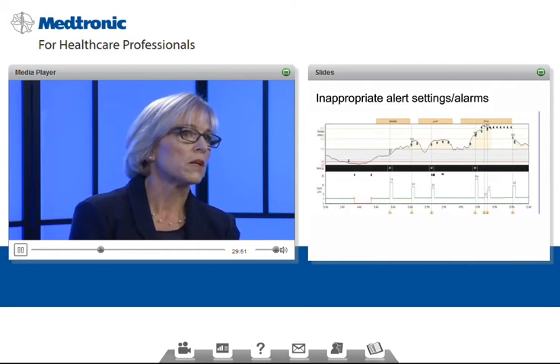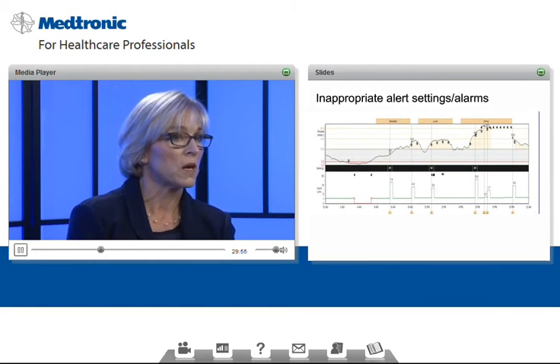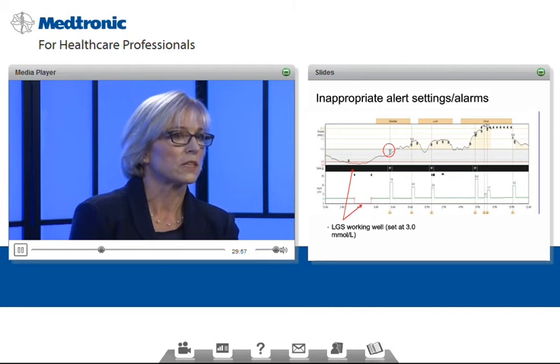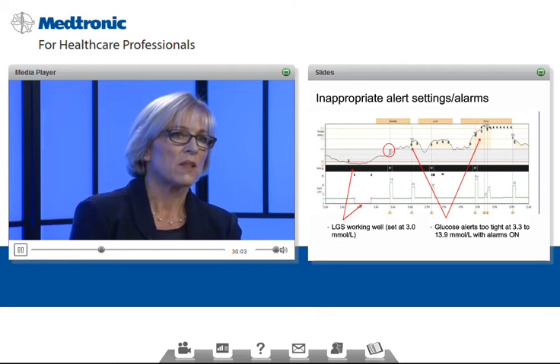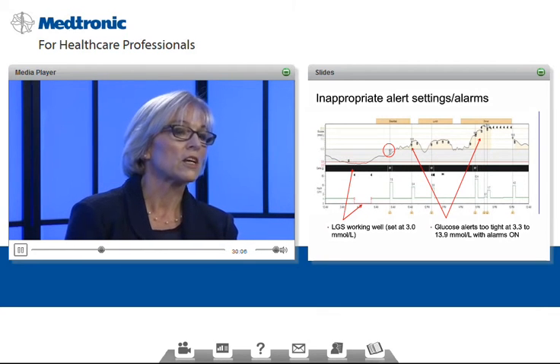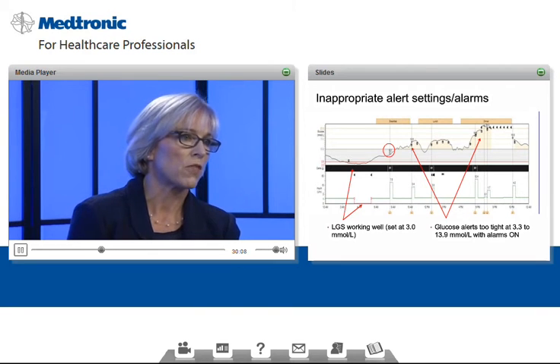This is an example of inappropriate alerts and settings, where you can see here, first of all, that low glucose suspend is working well. It's set at 3.0, and that's an appropriate setting. And the suspension led to a rise in blood sugar to 8.2 in the morning. But otherwise the alerts are set too tight, at 3.3 to 13.9. So alarms are occurring all the time, whether those be predictive alarms or glucose alerts. And someone who has this number of alarms is going to quickly stop using CGM because they're not getting benefit from it, and they're getting irritation.